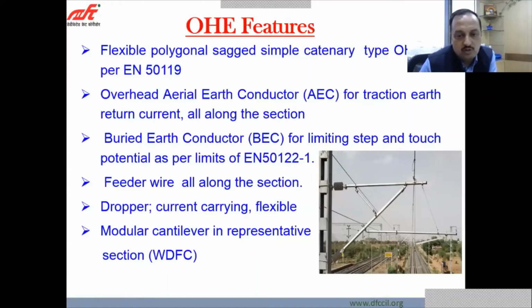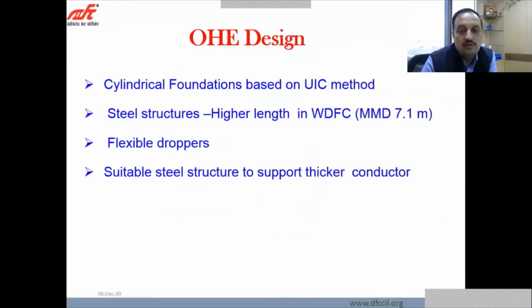Modular cantilevers have been adopted in a section of around 250 kilometers, just to gain experience of what the benefits of these cantilevers are in terms of maintenance, operation and all. If these are found to be beneficial, then they can be adopted for future corridors also. For the OHE design, cylindrical foundations have been used based on the UIC method. The steel structures are of higher length because of the high-rise OHE, because our MMD is at 7.1 meter level, so our OHE is also at 7.54 meter. Flexible droppers are used, and steel structures are suitable to support thicker conductors.